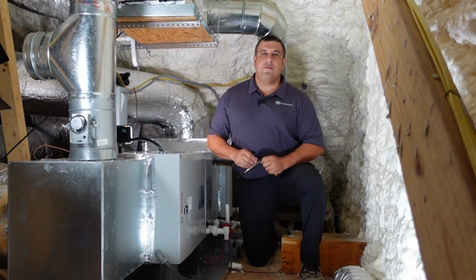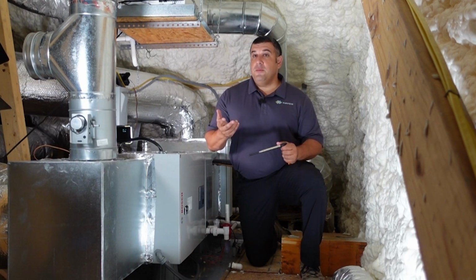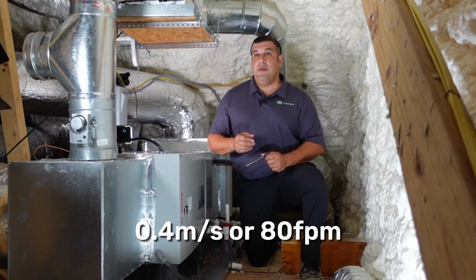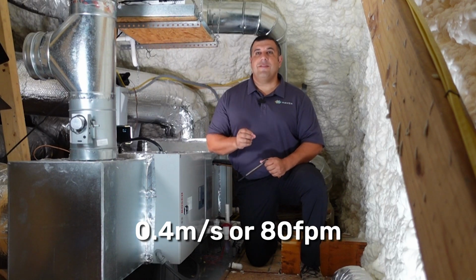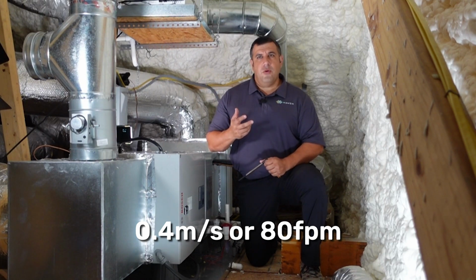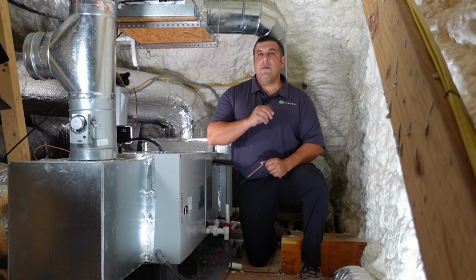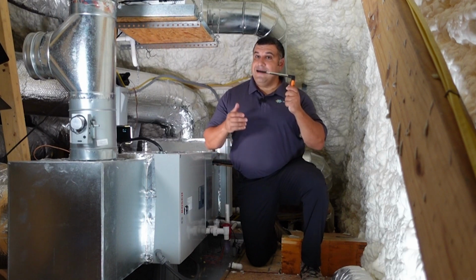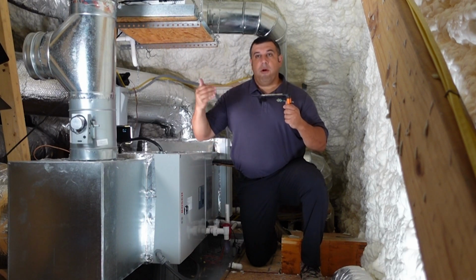Let's address air velocity here for a minute. Fan speeds must be between 80 and 1,200 feet per minute, or 0.4 to 0.6 meters per second. If you're not sure how the air is behaving in the intended installation location, we highly recommend using an anemometer to test the speed of the air before continuing.